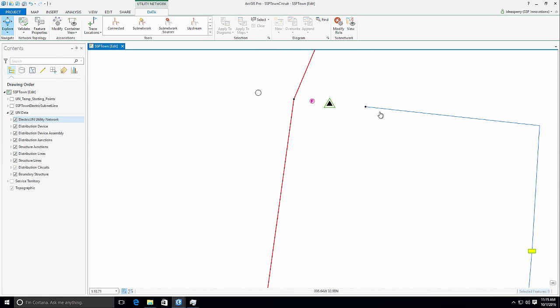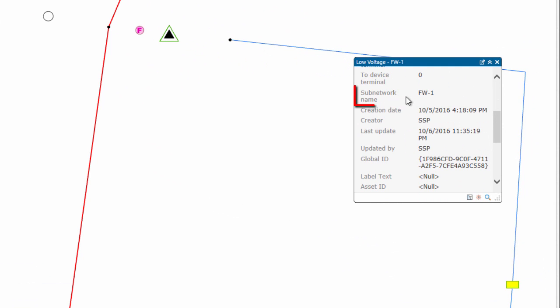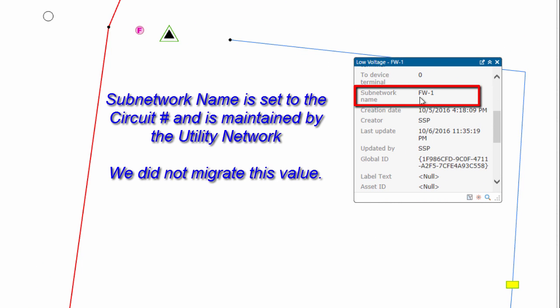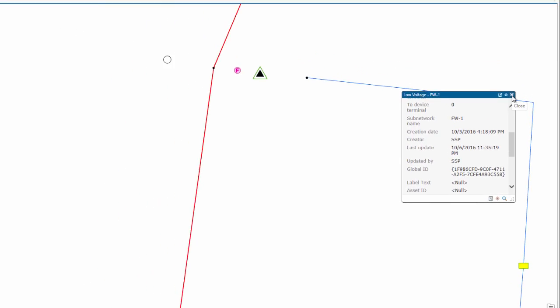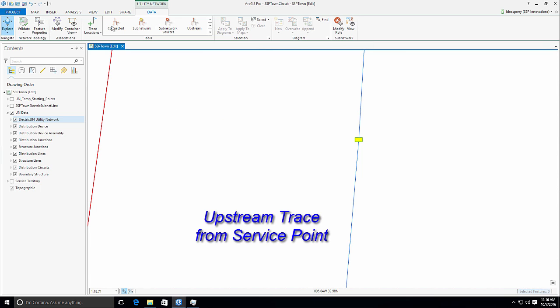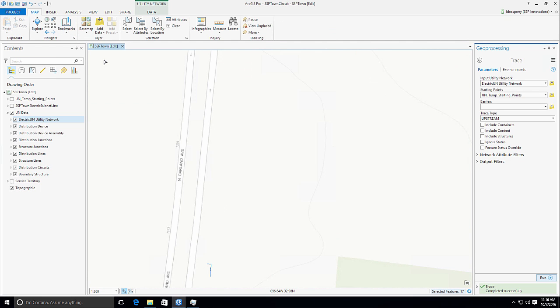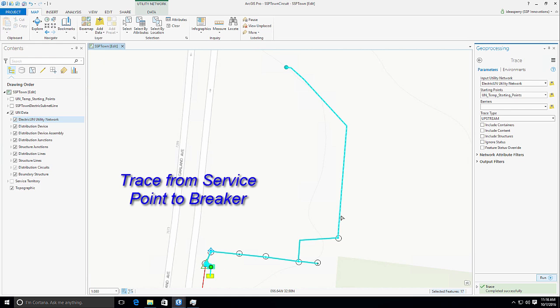Using our explore button, we'll take a look at the secondary record. We can identify this record and see that the attributes came across, but most importantly the subnetwork name — which is maintained by the utility network — has been set correctly to FW-1. That attribute was maintained as part of the circuit tracing and subnetwork management within the utility network. Next, let's run a simple upstream trace from this service point. We identify this point as our starting point for the trace location and run an upstream trace with default parameters. As we zoom out to the extent of the selected features, you can see that the trace has occurred and has traced all the way back to the source at the substation, performing a typical upstream electric trace.